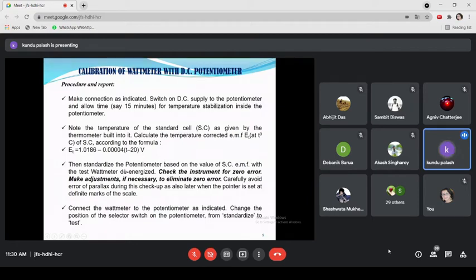But standardize the potentiometer based on the value of the SC EMF with the test wattmeter de-energized. That means the wattmeter, that is V1 and V2, will not be connected. Connect the wattmeter to the potentiometer upon standardization, that means when the null is obtained when comparing the standard voltage with the potentiometer potential drop. That is the objective of the standardization process. That means set the potentiometer wire current to such a value that the potential drop will be equal to the set value, the predefined value obtained by the standard cell.